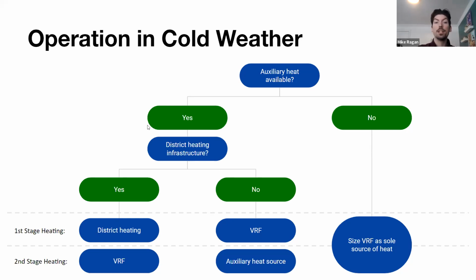How is the system set up? Is it a district heating infrastructure? Is it a campus style with just a single hot water pipe running through every single building, and it's going to be turning on, there's no way of turning it off, it's running through that radiator? If that's the case, there's very little we could do to stage it because it's still running through that radiator. So in that instance, we should use the district heating as the first stage of heat and stage your VRF as backup. Have the VRF pick up wherever the district heat is unable to achieve. If you don't have a district heating infrastructure, if you have individually zoned auxiliary sources, like radiant baseboard loops, electric baseboard loops, etc., there we would want to stage the VRF as the primary stage and have that auxiliary heat source be the backup, the second stage.